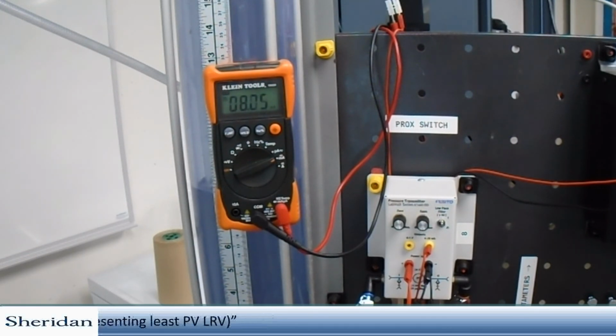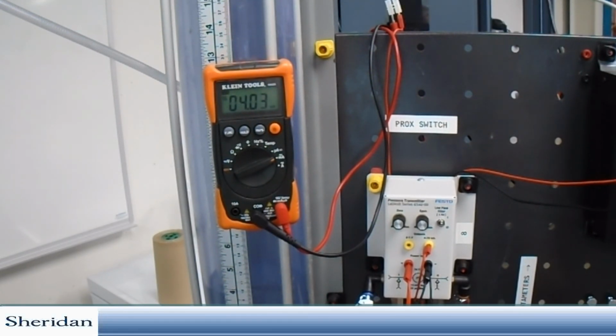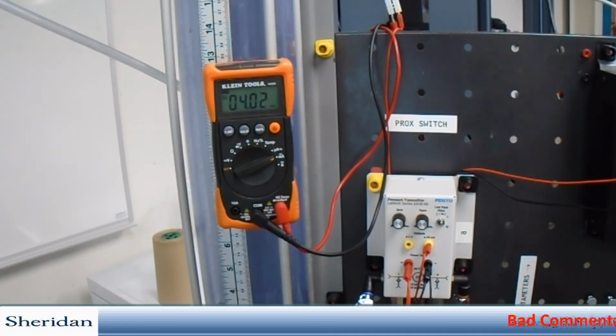While the water is going down, with the chart that you prepared last week, you should be able to get a gauge when it gets to around 10 inches, around 6 inches. You can check your numbers and see if you're close. So we're down to 3 inches, 2.5, and 2. And I'm still at 4.02 milliamps.